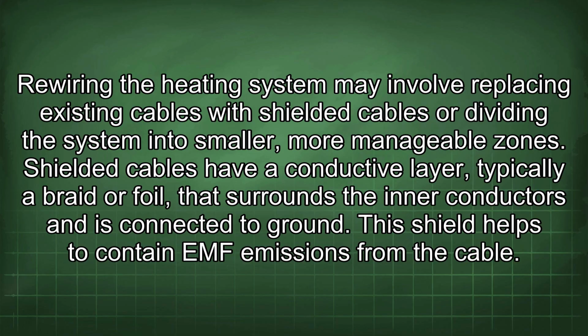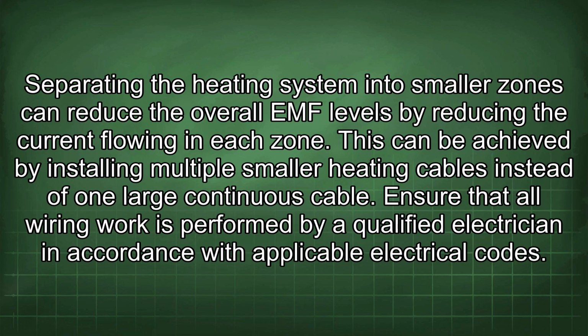Rewiring the heating system may involve replacing existing cables with shielded cables or dividing the system into smaller, more manageable zones. Shielded cables have a conductive layer, typically a braid or foil, that surrounds the inner conductors and is connected to ground. This shield helps to contain EMF emissions from the cable. Separating the heating system into smaller zones can reduce the overall EMF levels by reducing the current flowing in each zone. This can be achieved by installing multiple smaller heating cables instead of one large continuous cable. Ensure that all wiring work is performed by a qualified electrician in accordance with applicable electrical codes.